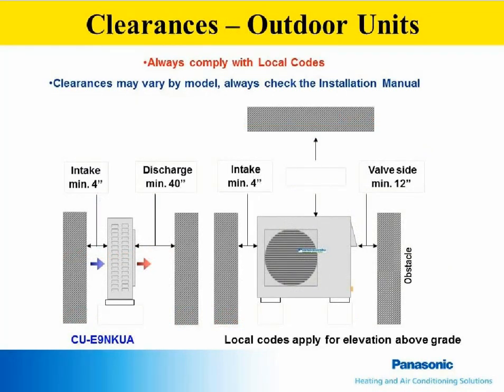All units have clearances that vary from model to model. Please take them into account when selecting a location for installation. In this example, the outdoor unit has a minimum 4-inch intake clearance. The coil is on the intake side, so 4 inches may or may not be enough room to clean and service the unit. The circuit boards for most models are accessed by removing the top panel, so take this into consideration also. No matter what the factory minimum clearances are, please make sure that the unit can be cleaned and serviced and that the discharge air does not recirculate back through the intake.